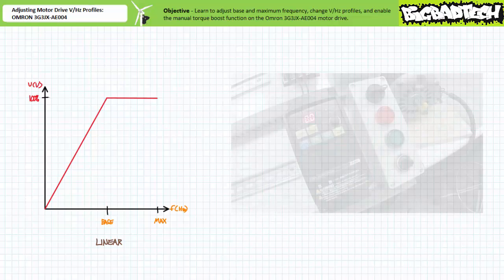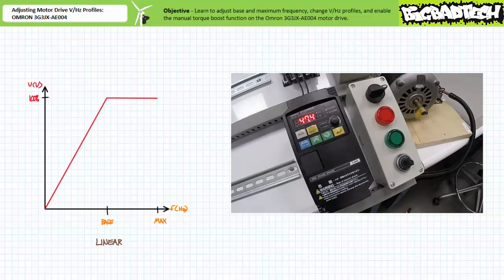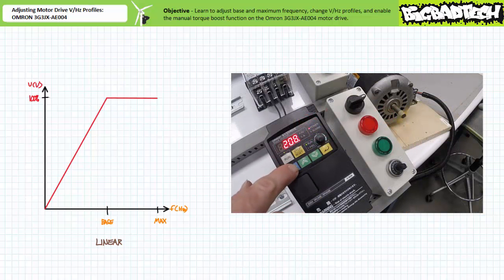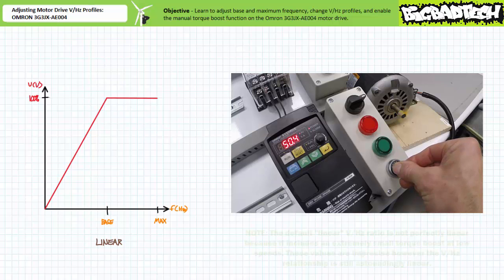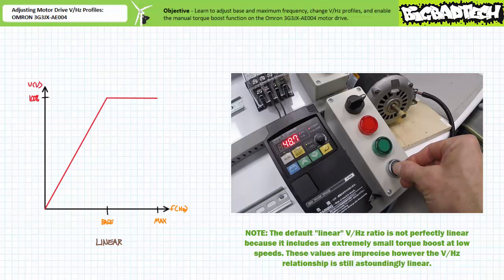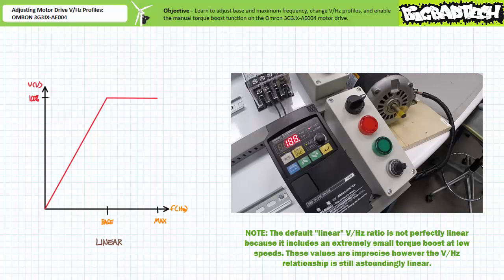When we start the motor with the external speed potentiometer pegged fully clockwise, excitation frequency ramps up to only 60 hertz this time, as we'd expect. The motor accelerates and speed stabilizes. While the motor is running, we can navigate to parameter D013, output voltage monitor, and find the motor drive is applying roughly 100 percent of the available line-to-line voltage. When we return to display parameter D001, the output frequency monitor, we can readjust it to provide a 48 hertz excitation frequency, or 80 percent of the base frequency of 60 hertz. When speed stabilizes, we can navigate back to parameter D013 and find the motor drive is applying roughly 80 percent of the available line-to-line voltage. Applied voltage as a function of frequency appears to be linear, with excitation frequency limited to the range 0 to 60 hertz.